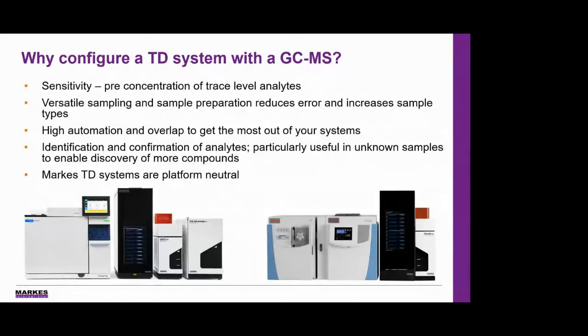The high automation of a TD-GCMS system, especially with the easy overlap mode, provides enhanced productivity, where the next sample can be loaded and desorbed while the GCMS is still running the previous sample. TD-GCMS can also be used for the identification and confirmation of analytes, which is particularly useful for unknown samples, enabling discovery of more compounds by spectrum matching with established libraries. Lastly, the Markes TD systems are platform neutral, meaning they can be added to any brand of GCMS, including existing systems, representing lower capital investment overheads.